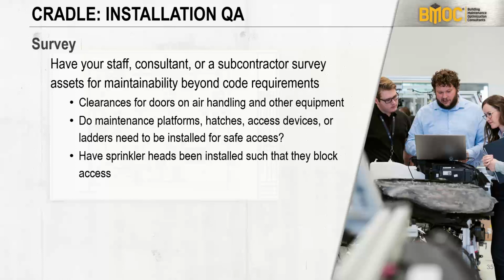Next, this is one of my favorites. Sprinkler systems are typically checked later in the project after all the equipment has been installed, and sometimes they have to move sprinkler heads. In many cases they have to. We've seen cases where those sprinkler heads get moved right in front of a fan coil unit, where you cannot open that hatch at all. It was one of those facepalm moments, pretty funny though, I have to admit. So watch for things like that even towards the very end of construction. Be prepared, so when that building gets turned over, make sure the subcontractors or general contractor are still on the hook to make late fixes like that.